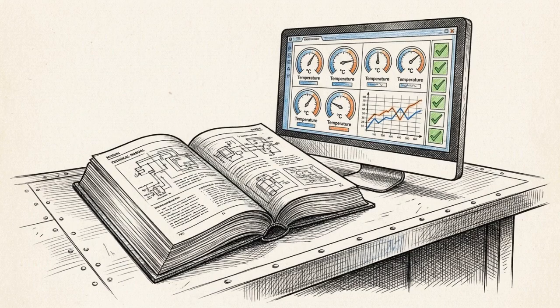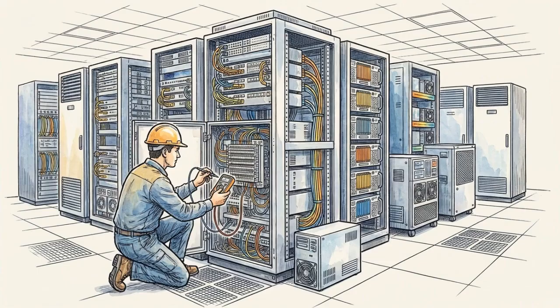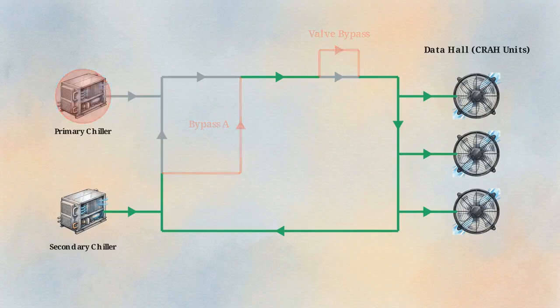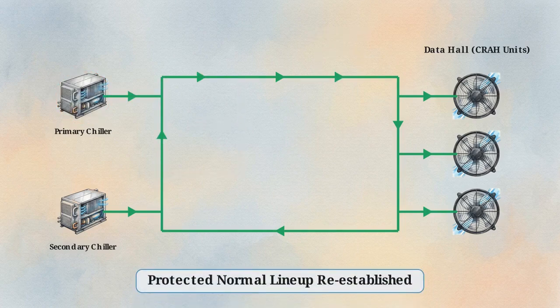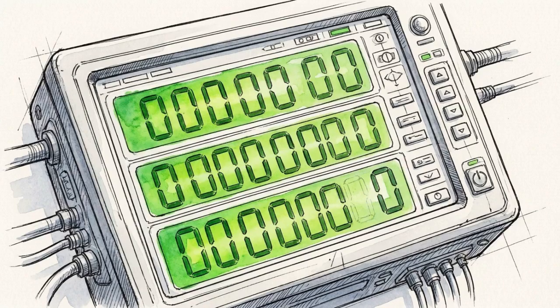At the core of this phase is the systems manual, functioning as the ultimate translation of design limits into usable operations. Operational competency sign-off must be strictly performance-based. True competency is demonstrated through live fault isolation drills, not merely confirmed by attendance. Following any drill or test, rigid restoration protocols dictate exactly how the facility is returned to a protected normal lineup, ensuring the definitive clearing of all temporary overrides and stale alarms.